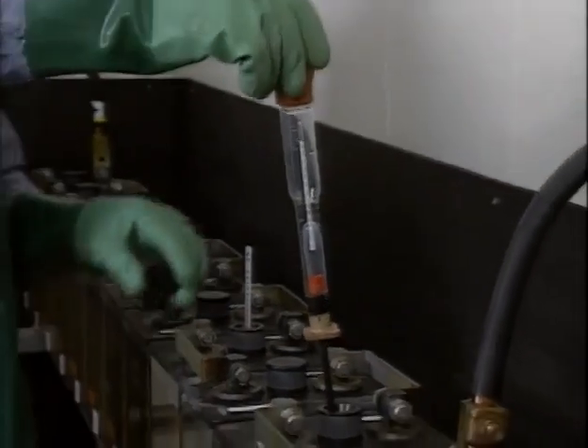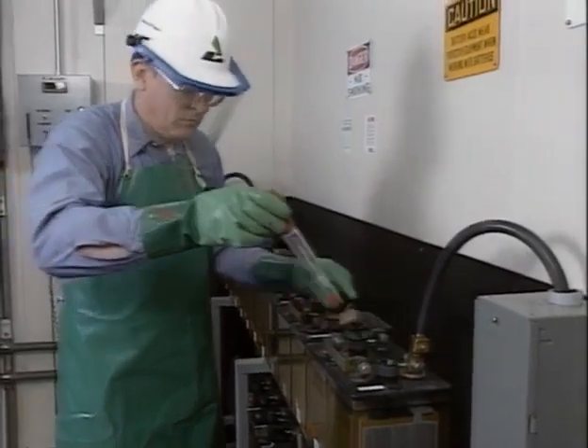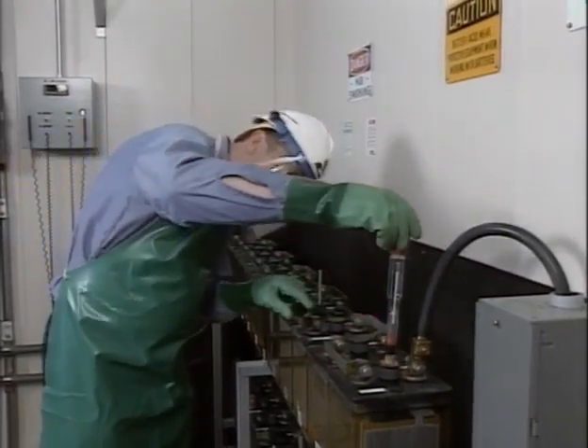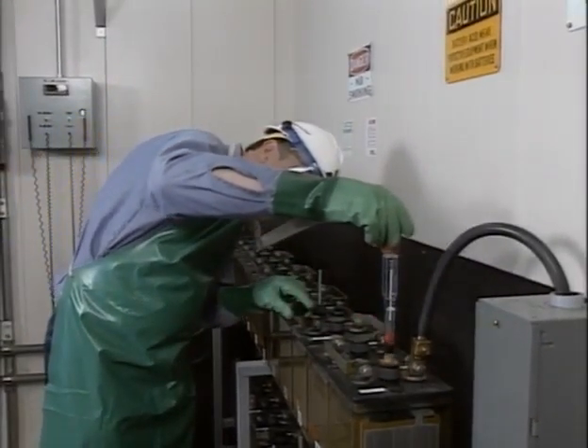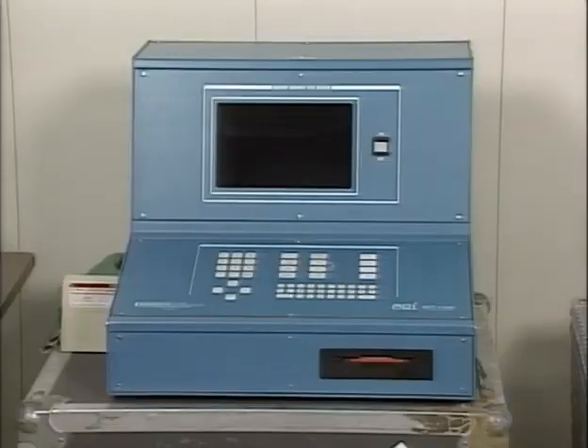Specific gravity tests, if done at the right time and when properly corrected for temperature, give a good indication of the state of charge of the cells in a battery. Now, while specific gravity and voltage tests indicate the state of charge of the cells in a battery, they don't tell you if the battery can deliver the necessary power when it's needed. Two tests that do are the integrity and capacity tests. These two tests will be covered in the next part of this program.